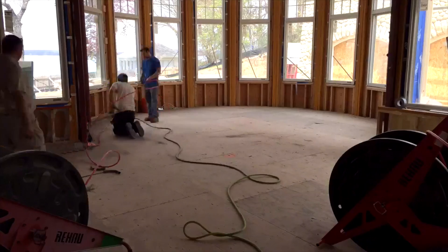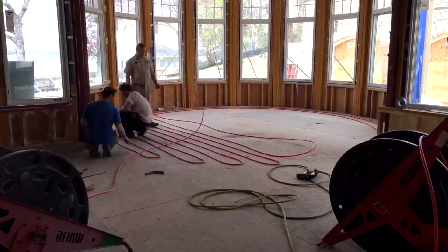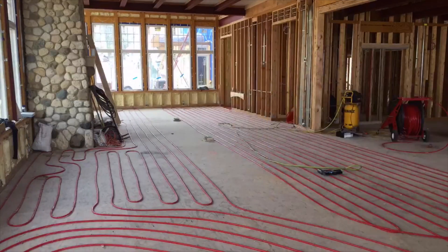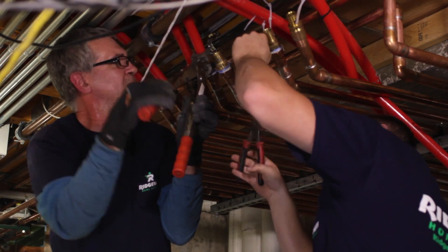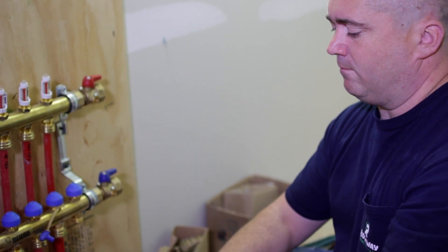We use REHAU O2 barrier tubing for radiant heating in the floors. The majority of this installation is staple-down floor radiant heating. We put in over 9,000 linear feet of tubing in this project. We have over nine different floor radiant zones, all controlled by REHAU thermostats with in-floor sensors. The project is designed for floor warming of the house. Throughout the home, we have used remote manifolds from REHAU — they're pro-balance.